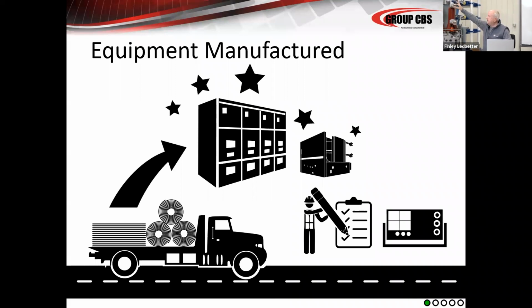Okay, they connect through primaries into the cell. This is one of our breakers. This is one of our replacement breakers, for instance, that would plug into a piece of switchgear. Now, the breakers are also assembled in a breaker assembly plant, which sometimes is part of the same plant. Sometimes they're assembled down the street or in a sub-supplier and then shipped into the switchgear plant.